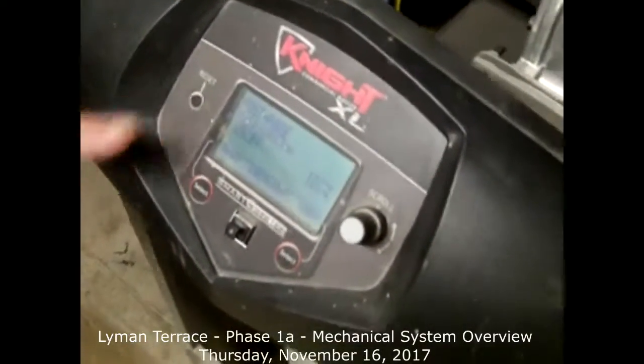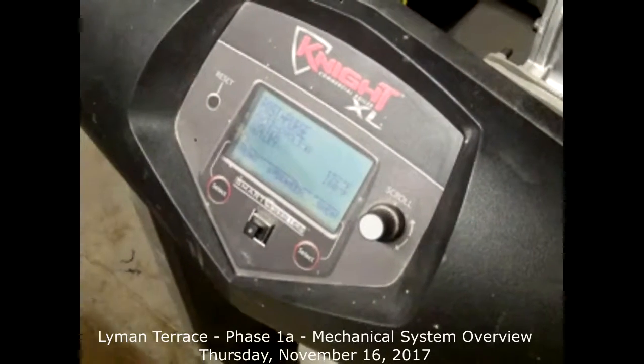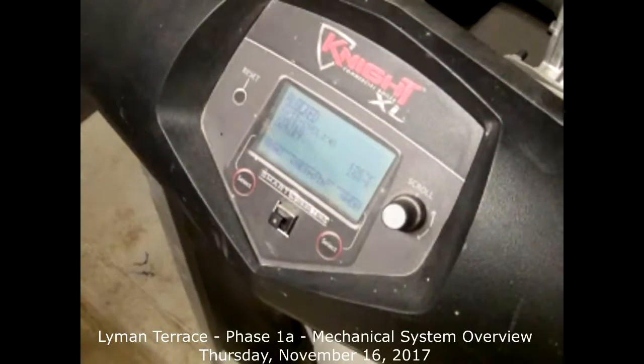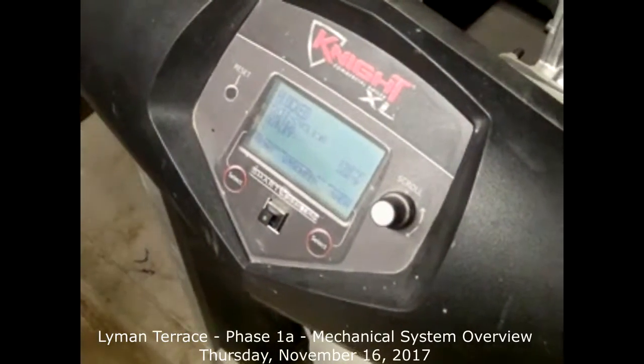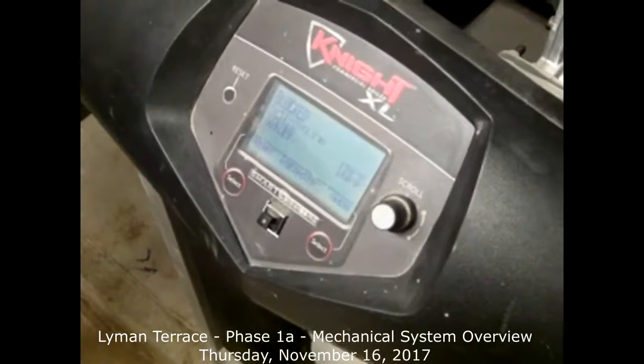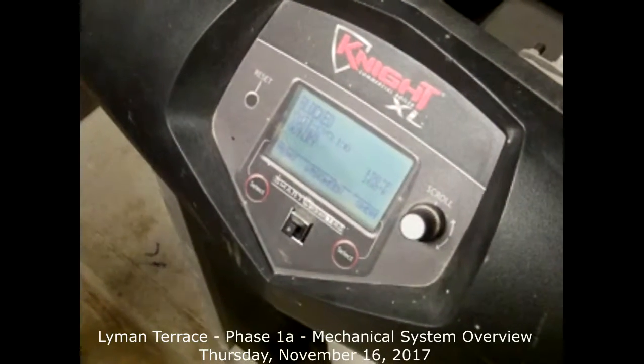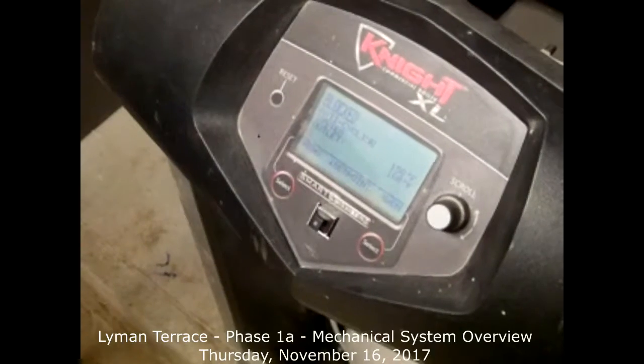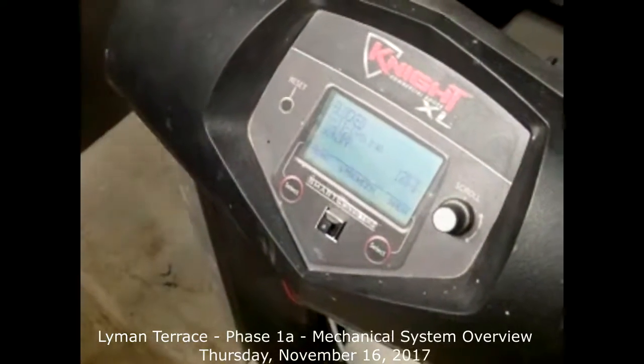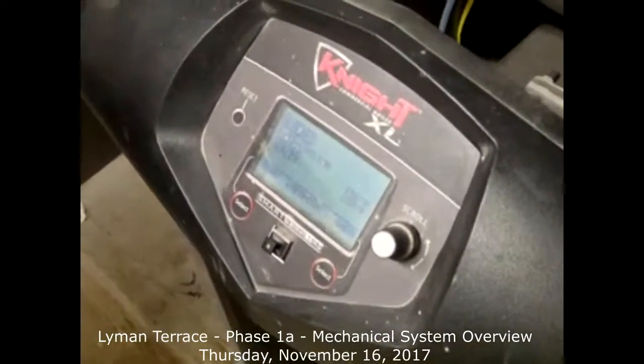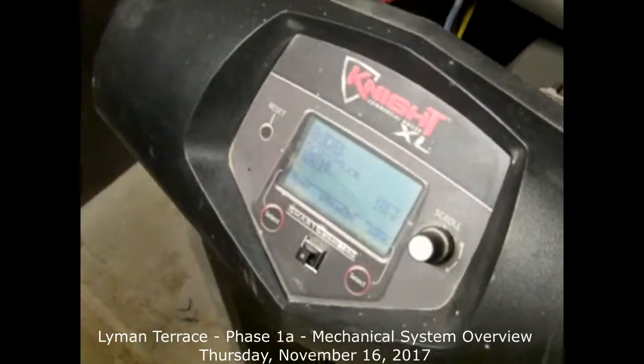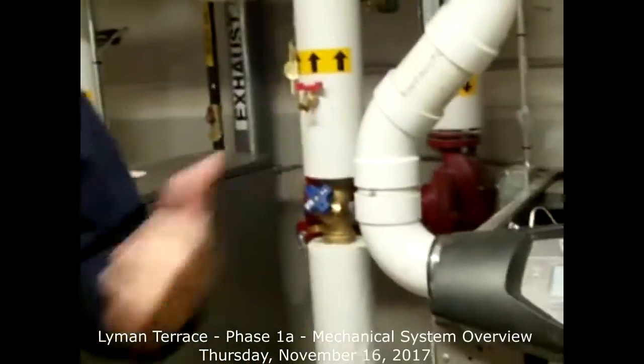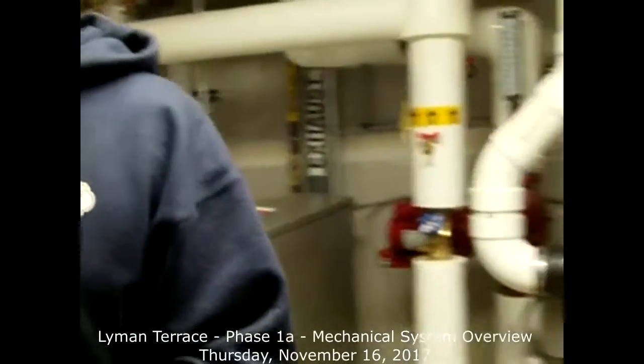And now it's in post-purge, and what that means is it's expelling any of the gases out of it that were inside, being combustion or natural gas and air mixture, and it will vent it outside, and the boiler has stopped. After a few minutes, the pump will stop, because what that's doing is equalizing the temperature of the boiler and the loop, so that you're not just stopping a very hot boiler in its tracks. Gotcha. Now the pump shuts off at a time delay, so we've equalized our temperatures. Cool.